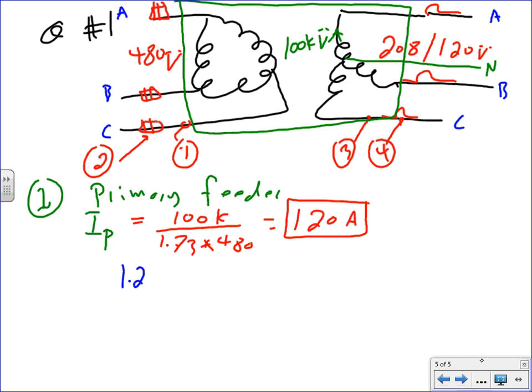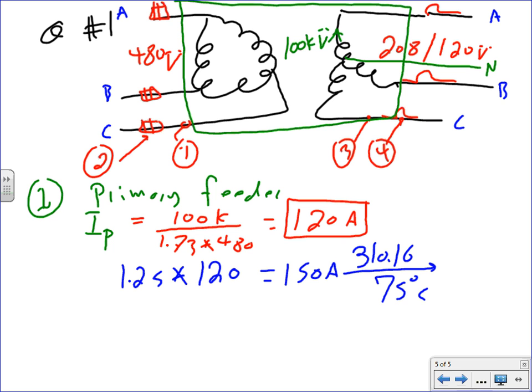So you take 1.25, multiply it by 120, and that will get you 150 amp. If you take this to 310.16, under which column? The 75-degree column. What do you get? How many conductors on the primary side? Three conductors, 1 aught. What insulation? Most likely THHN. 1 aught. Any question, guys? Straightforward, no gimmicks, nothing.